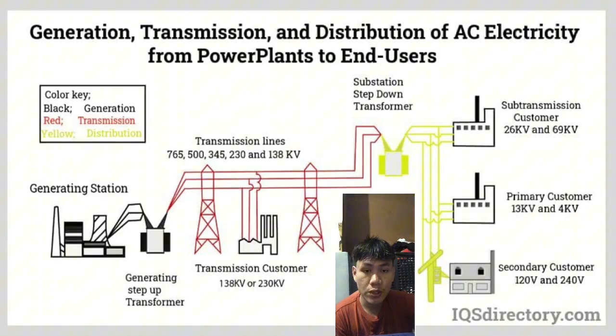After leaving the substation, electricity flows through distribution lines, shown in yellow in the image. These lines carry power to primary customers such as commercial buildings, small industries, and large establishments, usually at 13 kilovolts or 4 kilovolts in Tacloban. LEECO's distribution network spreads across barangays, ensuring that electricity reaches various consumers reliably. At this stage, the voltage is too high for household use, so additional transformers are needed closer to the end users.